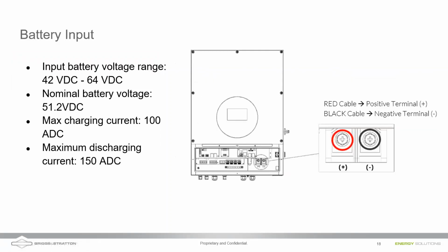All right, moving on. Battery inputs here on the inverter. So we've got an input voltage range from 42 to 64 volts DC, a nominal battery voltage of 51.2 volts for the input, and a max charging current of 100 amps DC, with the max discharge being a little higher at 150.